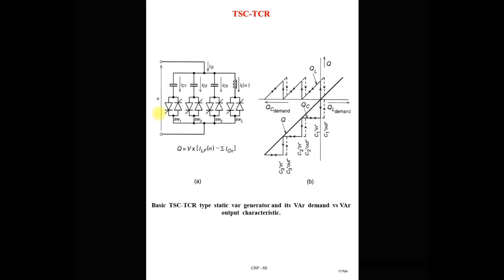First, here you can see the IQ reference. IQ reference is the amount of current required for the compensation of the system. So IQ reference is the total amount of current required at the system. It means IQ reference is the actual current required to maintain the voltage at the load bus near the rated value. Now this total current, IQ reference, is divided by each capacitor branch current. You can see that this TSC has the capacity to flow the current IC1, and the total reactive power current requirement is IQ reference. So this IQ reference is divided by each TSC branch current, so that we calculate the approximate integer number, and the nearest integer number gives the total number of TSC branches required.